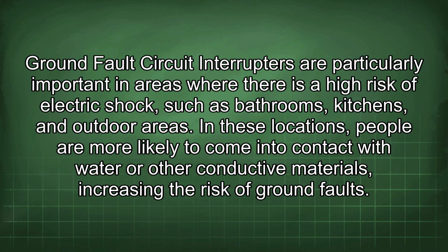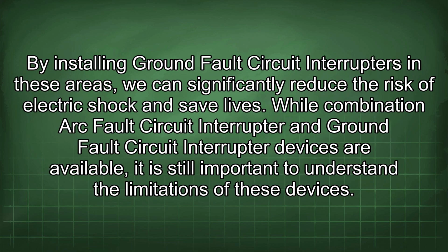Ground fault circuit interrupters are particularly important in areas where there is a high risk of electric shock, such as bathrooms, kitchens, and outdoor areas. In these locations, people are more likely to come into contact with water or other conductive materials, increasing the risk of ground faults. By installing ground fault circuit interrupters in these areas, we can significantly reduce the risk of electric shock and save lives.